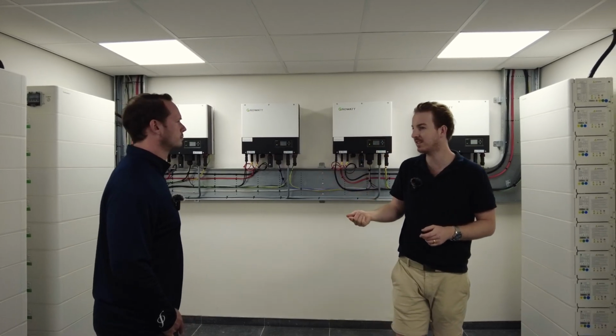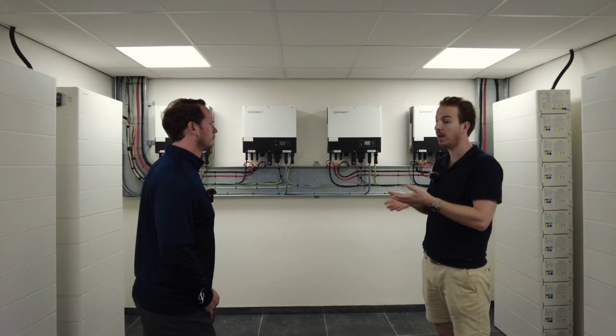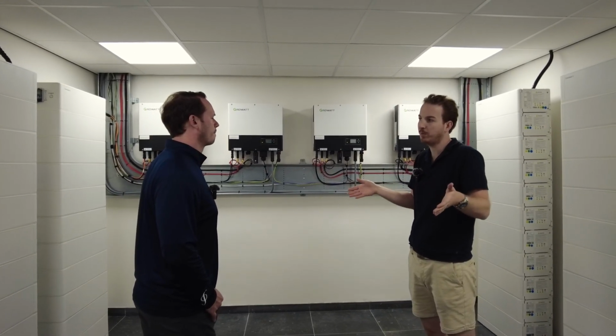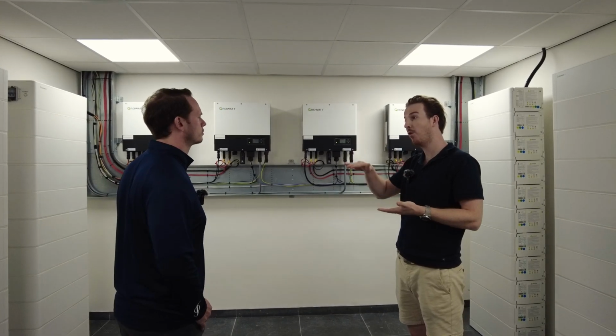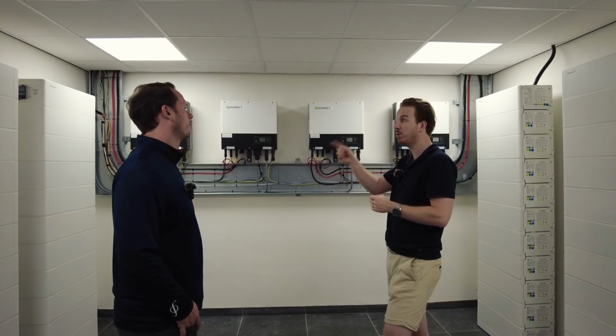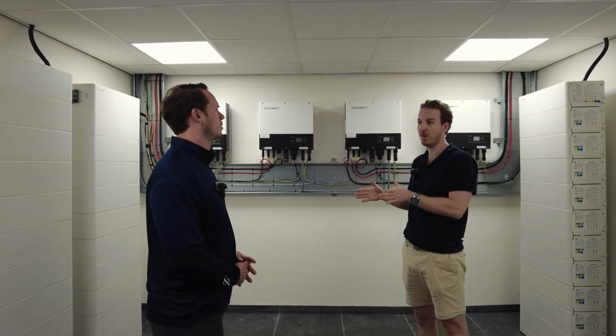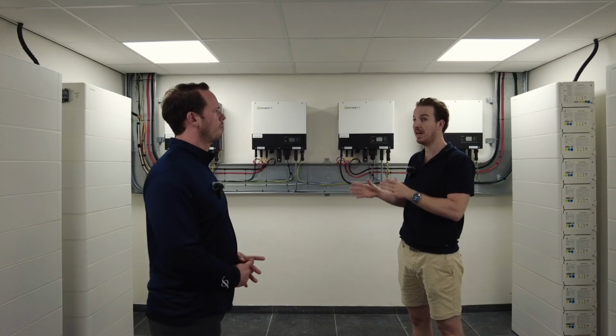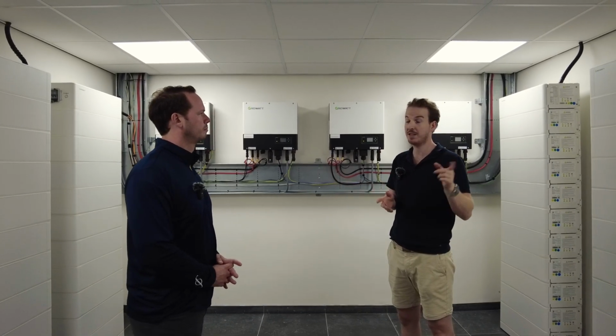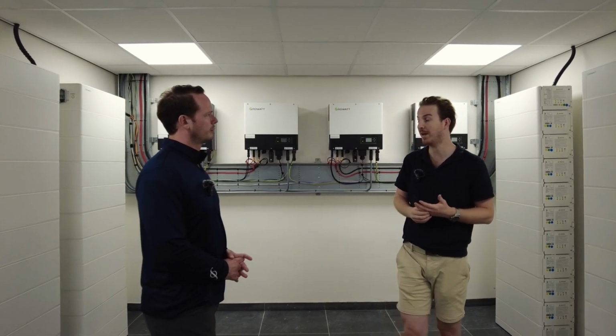And when the sun sets, the power prices slowly go up. And we don't pay a static price, we pay hourly rates, because on average it's cheaper. But these hourly rates between 8 and 10 in the evening are most expensive. So we put the battery systems to discharge during these expensive hours. So a few hours a day the data center runs on battery power, a few hours a day the data center runs on solar arrays, and during the night, of course, we use the main grid.